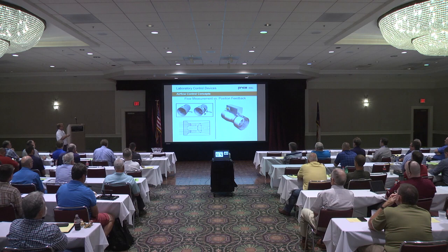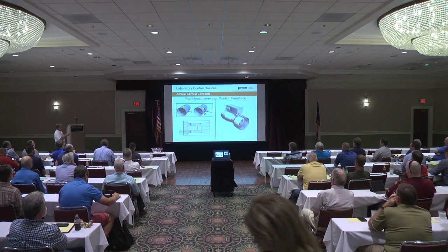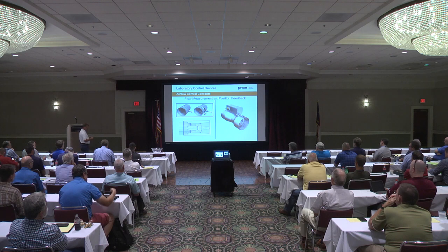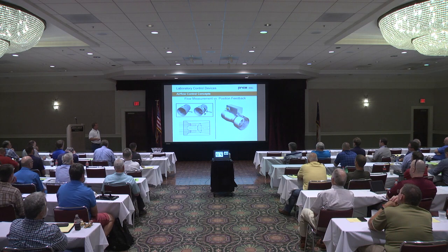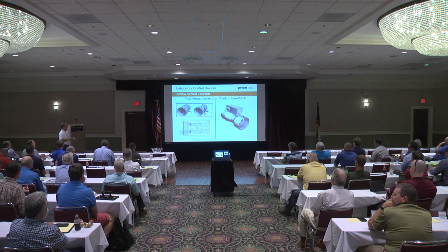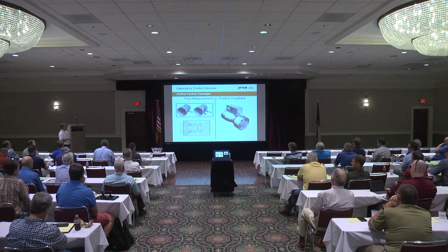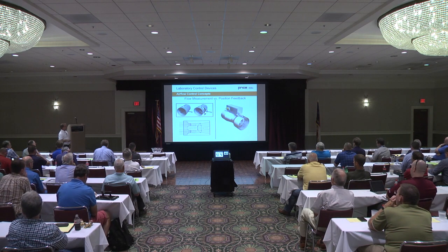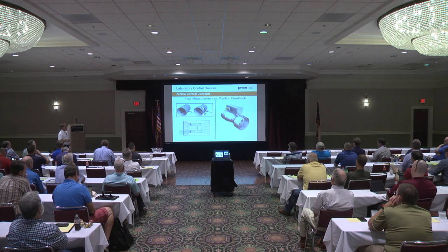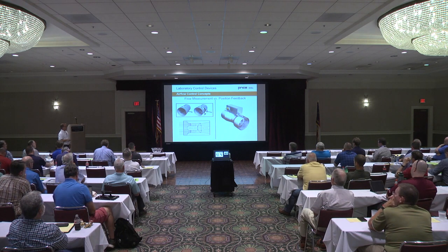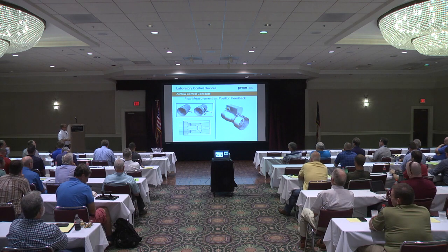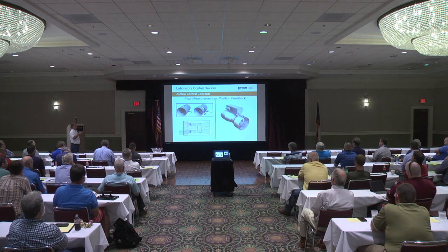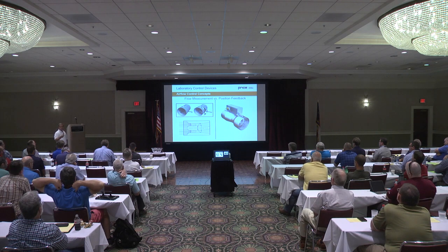So here's a couple of different airflow devices. There's your vortex shedding device. You can see in the center section it's kind of blocked out. It's got a flow sensor on either side, and a damper that's opening and closing, and that flow sensor is driving that damper to maintain flow. The top one's your cross flow sensing device showing the removable panel for cleaning, which is very important to consider, or at least have knowledge of, because you're probably not doing the design.